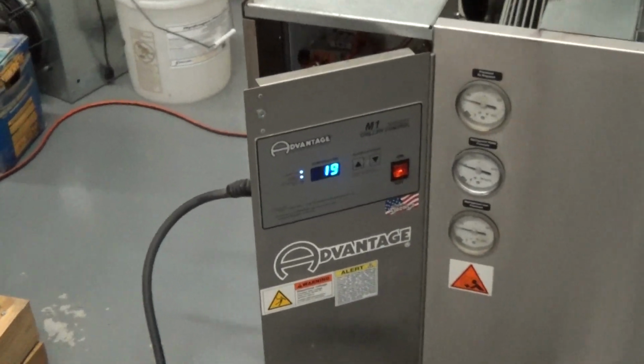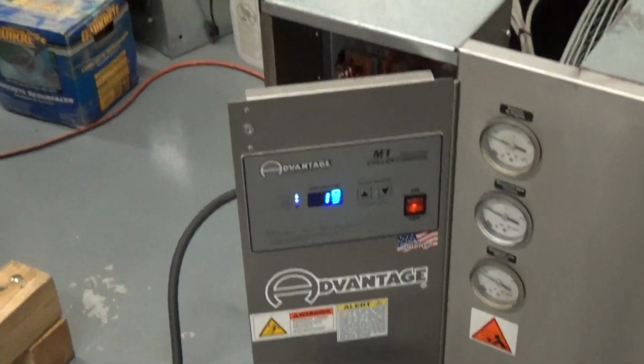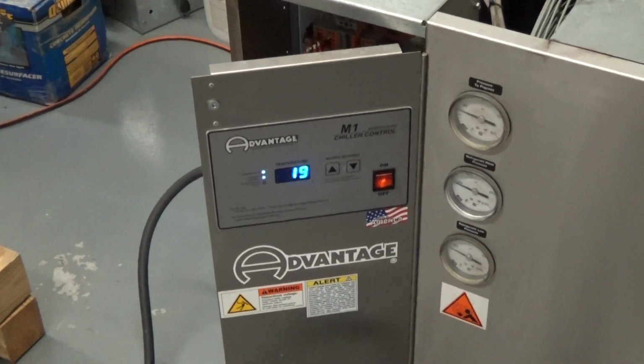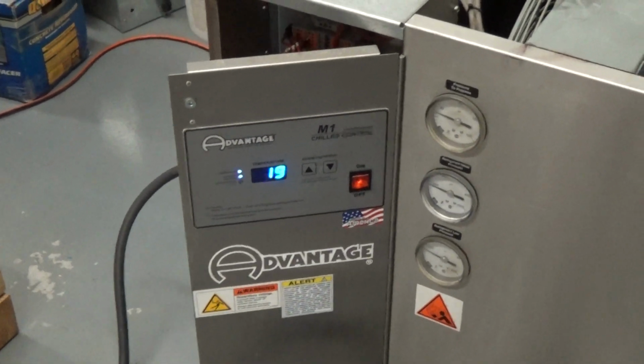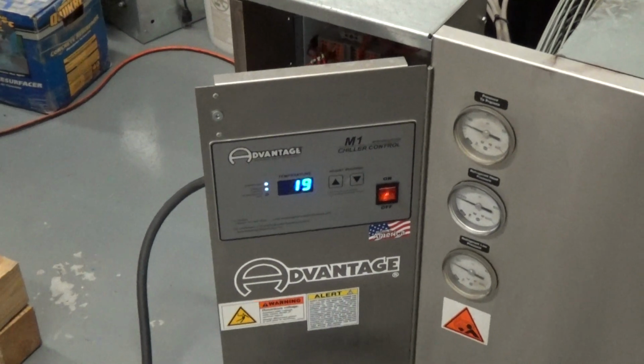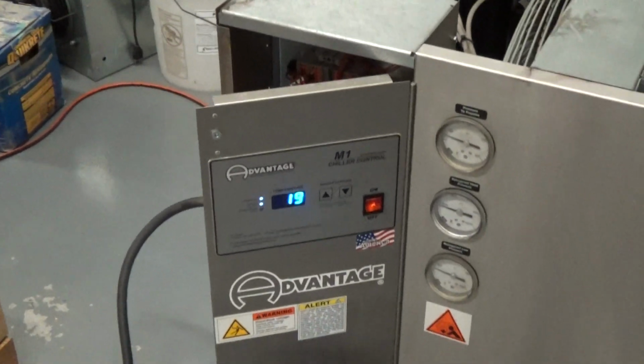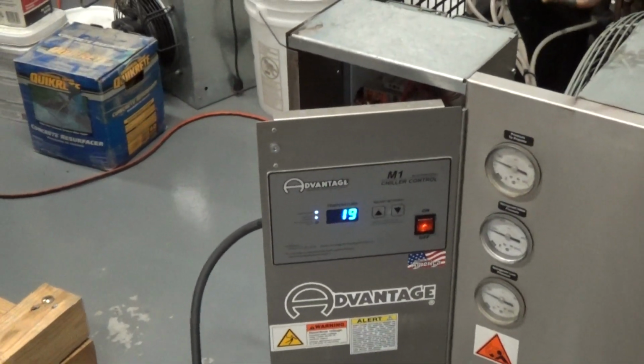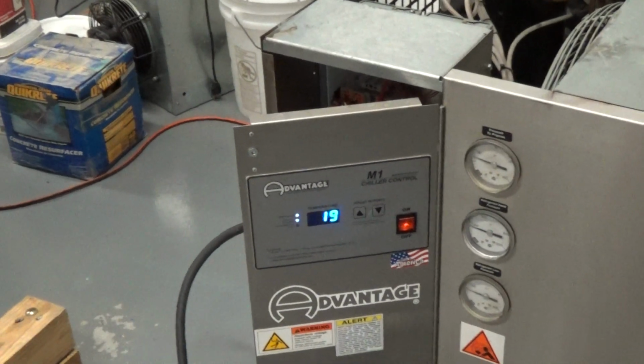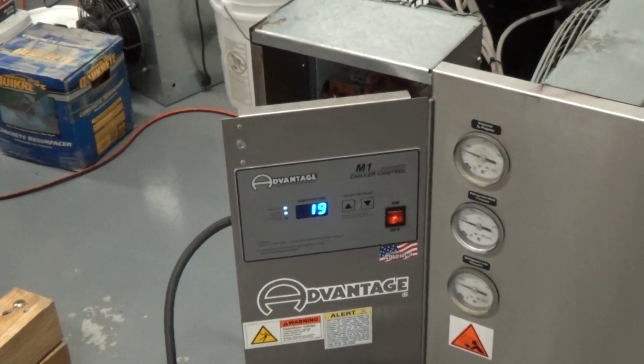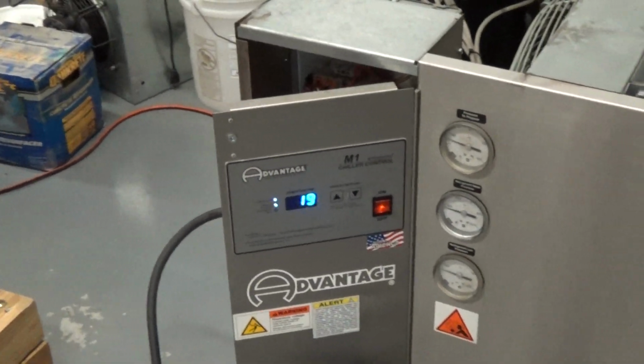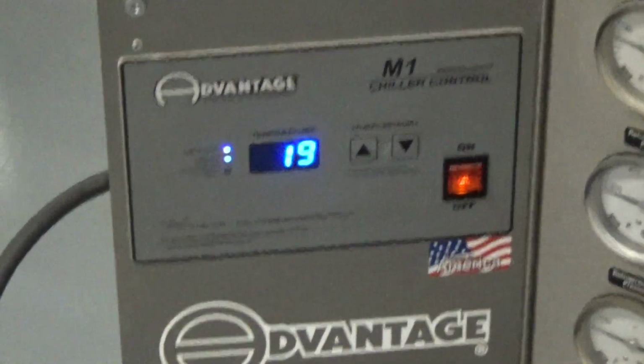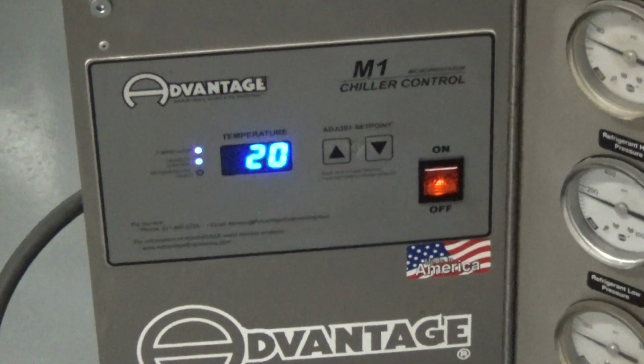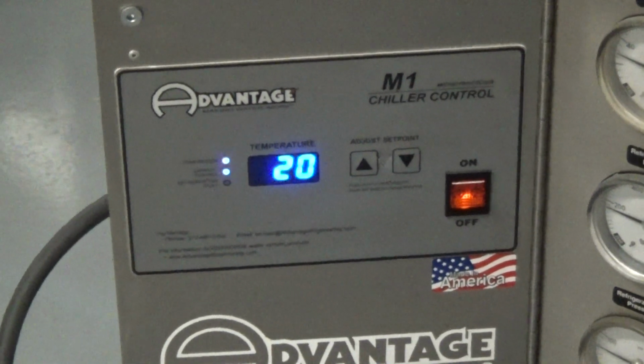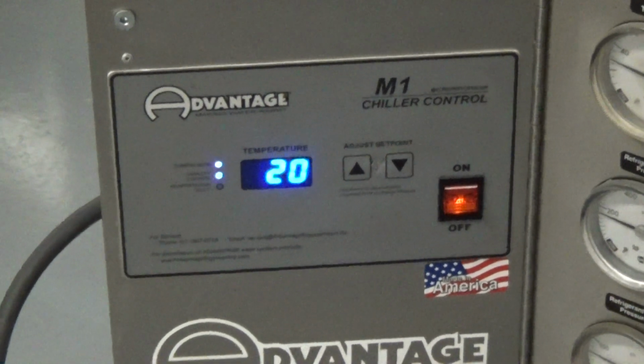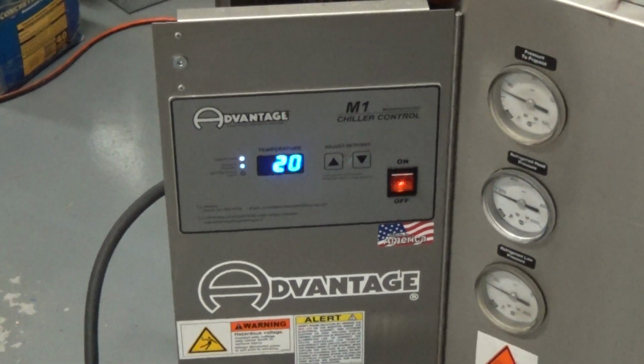We don't have hard copies of manuals, but we can shoot you over, or we probably already posted online, the soft copy for this manual. While I was just talking there a few seconds ago, you probably just heard the hot gas bypass solenoid valve click on. It slows down the rate of cooling a little bit. The whole idea is you want to minimize starts and stops on a compressor. Last thing you want is the compressor turning on and off once a minute. They like to be running for a certain period of time, and they like to be off for a certain period of time. Because at this colder temperature that hot gas just turned on, we might just sit there for a little while, which is good.